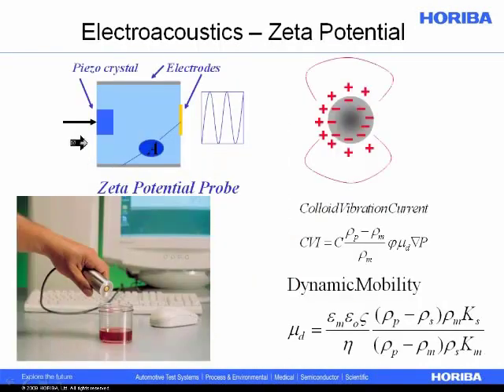This is a picture of the instrument used for those acoustic studies — the DT-1201. The sample is just added here, often without dilution. We have a transducer and a detector, and we look at attenuation as a function of distance between the transducer and the detector. In the same instrument we can also measure the charge on the surface of the particles — zeta potential — using an acoustic zeta potential probe, or CVI probe.